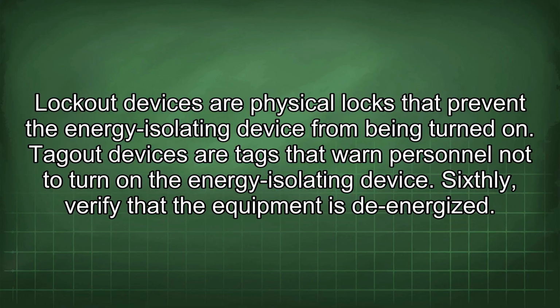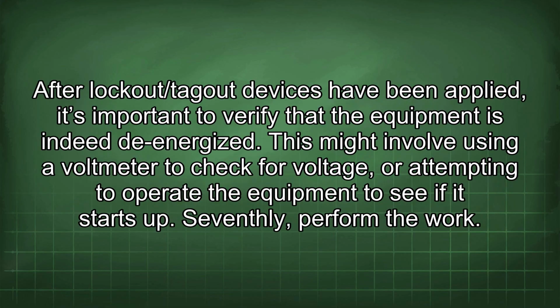Sixthly, verify that the equipment is de-energized. After lockout/tagout devices have been applied, it's important to verify that the equipment is indeed de-energized. This might involve using a voltmeter to check for voltage, or attempting to operate the equipment to see if it starts up.